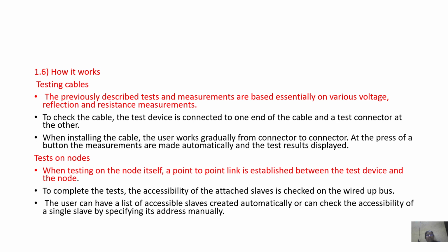So how it works: the previously described tests and measurements are based essentially on various voltage, voltage reflection and resistance measurements. To check the cable, the test device is connected to one end of the cable and a test connector to the other. For tests on the nodes, when testing on the node itself, a point-to-point link is established between the test device and the node. To complete the test, the accessibility of the attached slaves is checked on the wired bus.